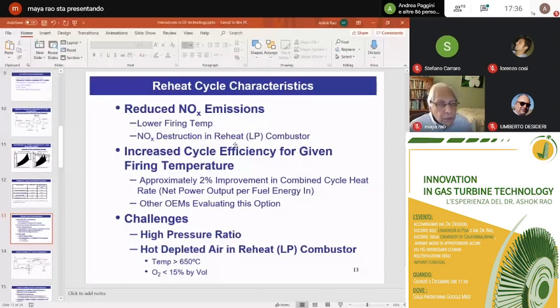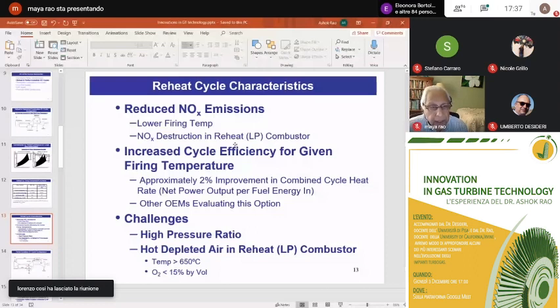Now, there's another approach to the reheat cycle that is also being looked at. Gas Research Institute in the US was heavily involved in this, and the US DOE was supporting it. Here we are partially combusting the fuel in the first combustor, the high pressure combustor of the gas turbine. So what you get is combustion products that are not CO2 and water vapor, but instead mostly CO and hydrogen. Then this is expanded again in an HP turbine, partial expansion, then going into the second combustor, the reheat combustor or the oxidizing combustor, where the combustion is completed. And then you go to the LP turbine.